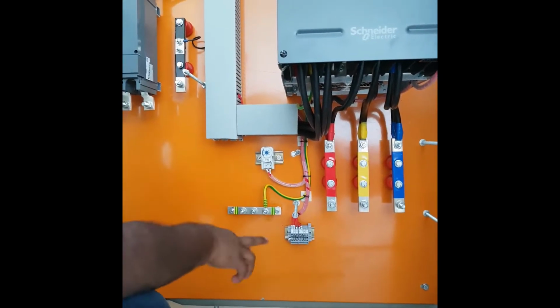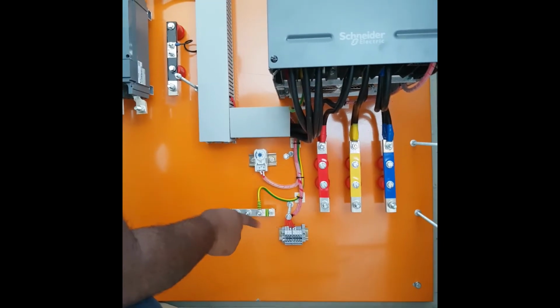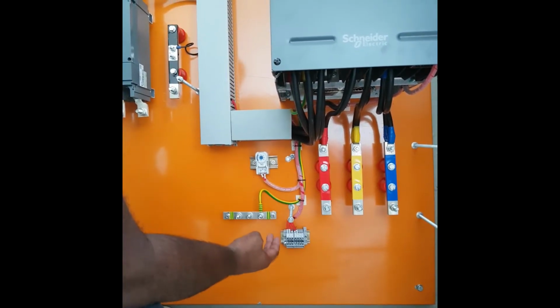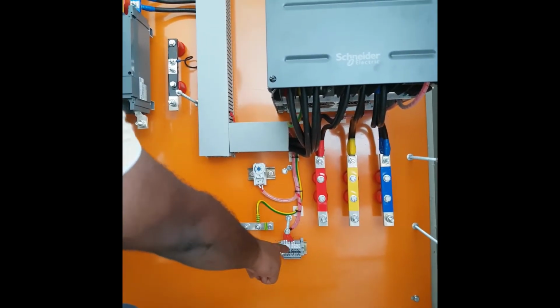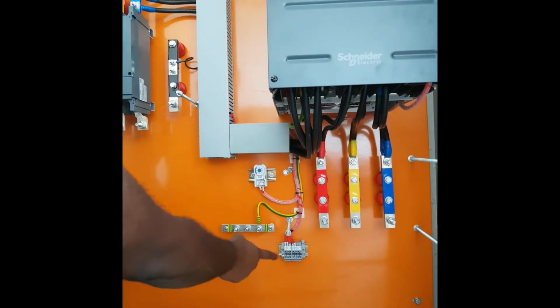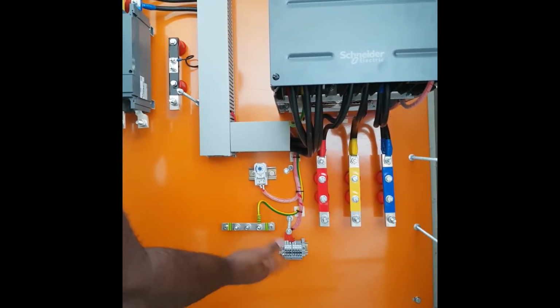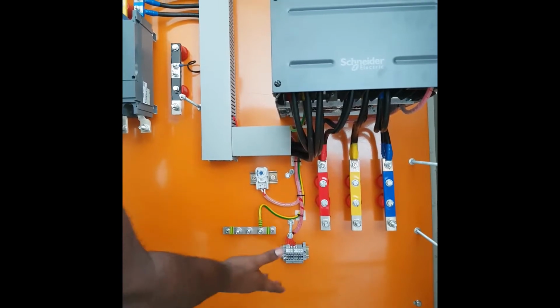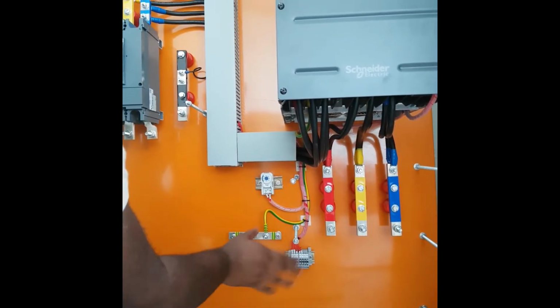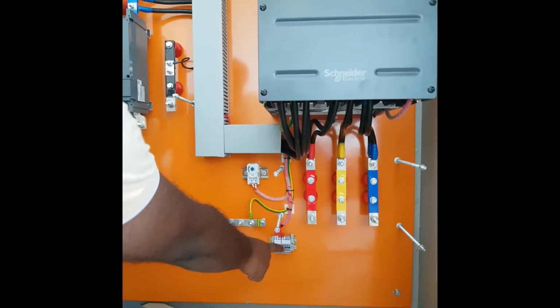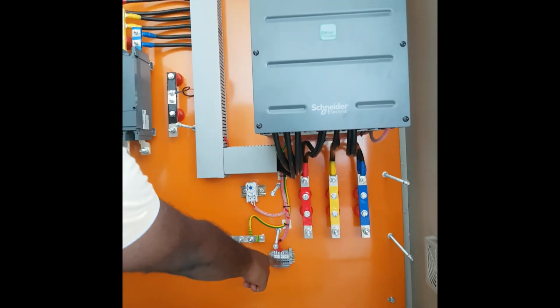Okay, and the other 2 terminals are for auto side, remote command. Through these two terminals you can connect any start command from a PLC or BMS or any level float or any remote switch, whatever you want. And if you select auto side, you can stop this panel from these 2 terminals.